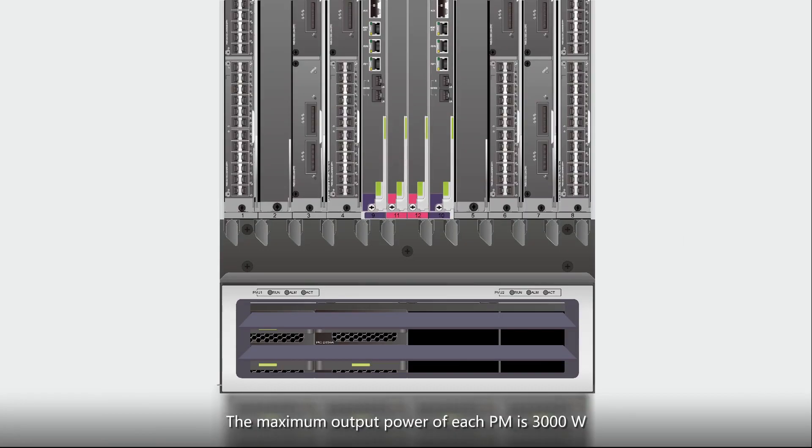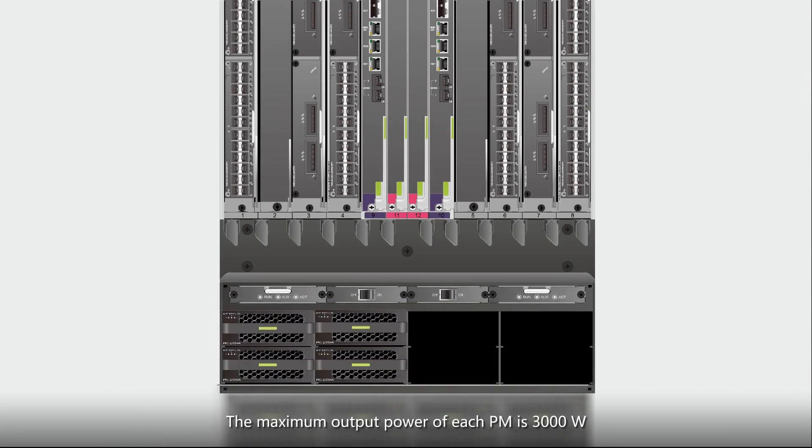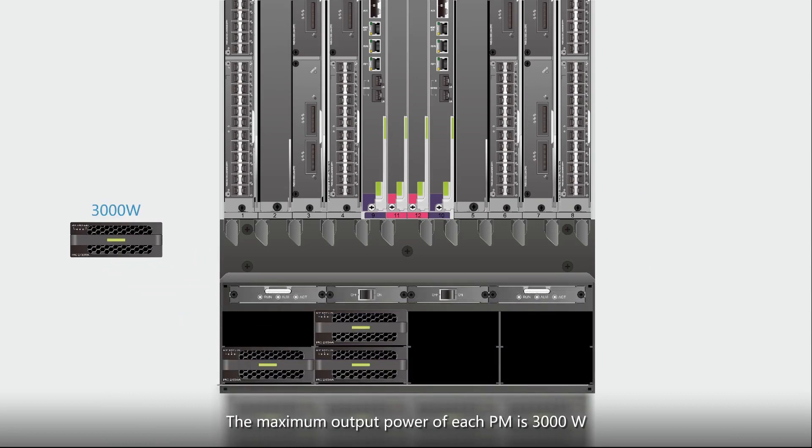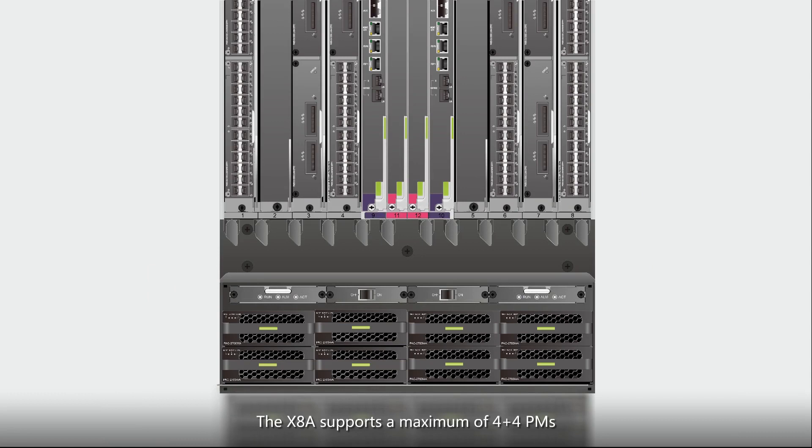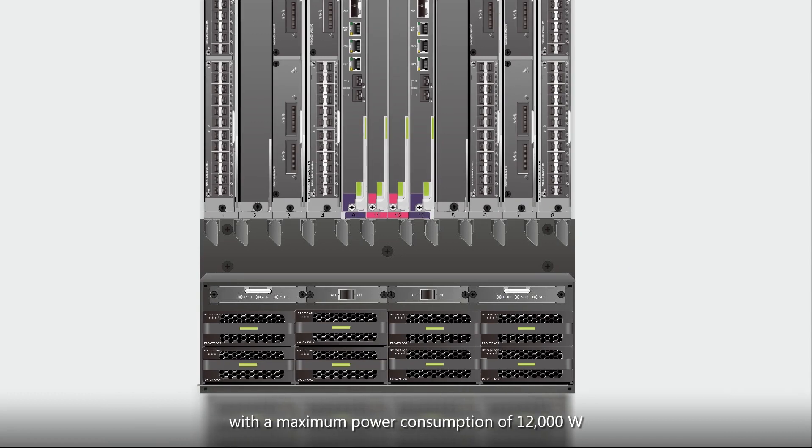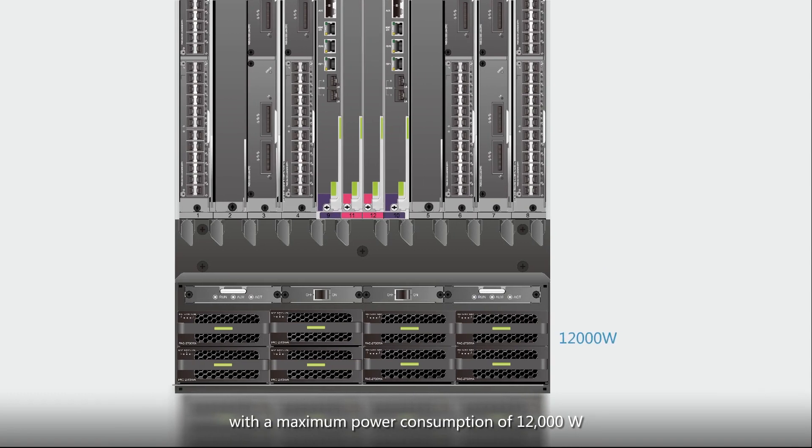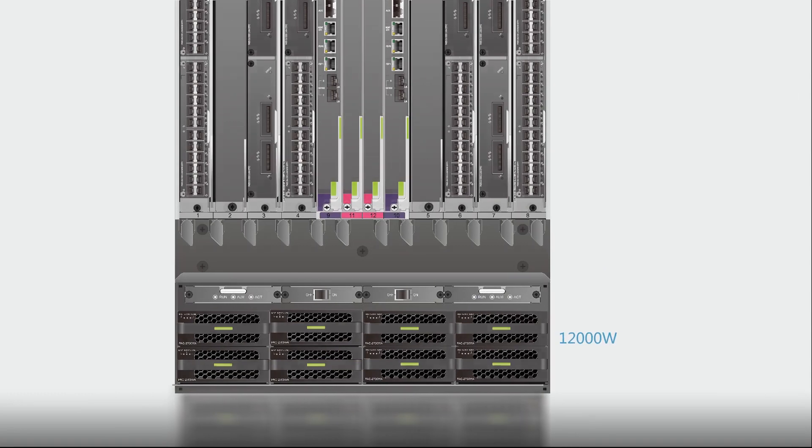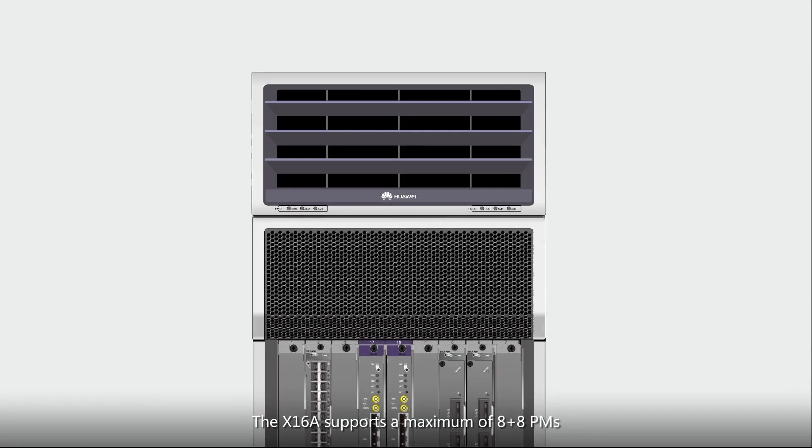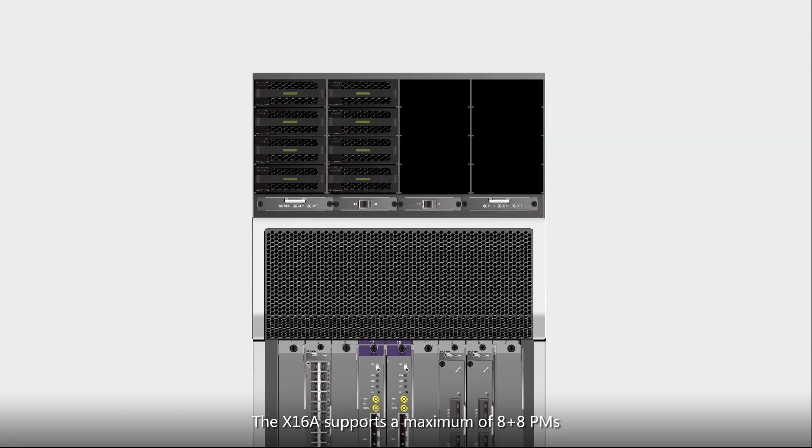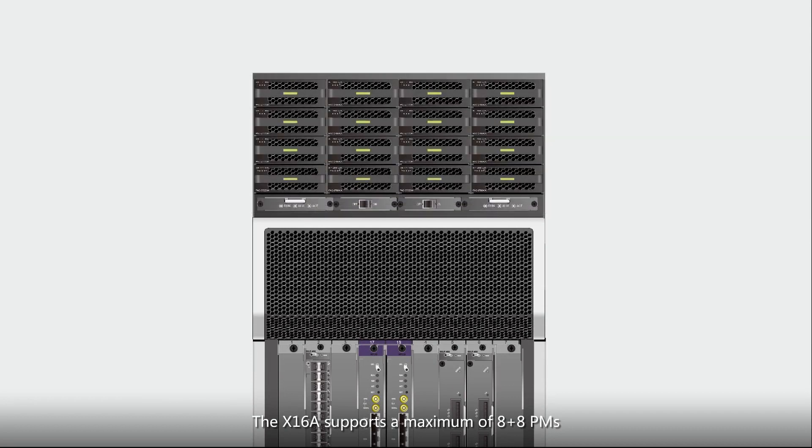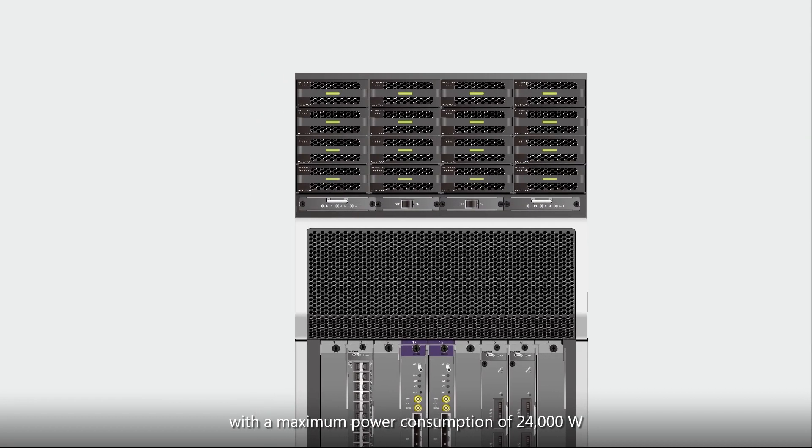The maximum output power of each PM is 3000W. The X8A supports a maximum of 4 plus 4 PMs with a maximum power consumption of 12000W. The X16A supports a maximum of 8 plus 8 PMs with a maximum power consumption of 24000W.